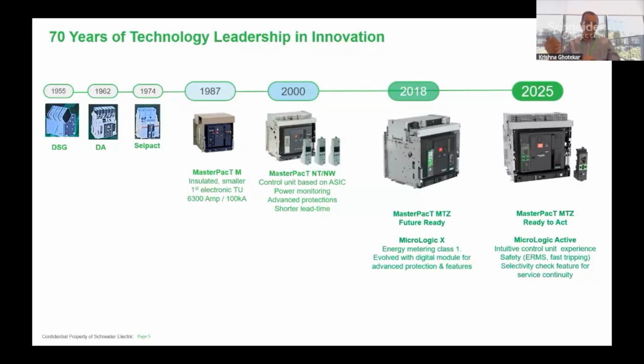Now this Active is basically an upgrade or addition to our existing MasterPact MTZ-X type of breaker. So MasterPact MTZ-X is for the high-end features for high-end applications like mission critical applications, whereas MasterPact MTZ, which is ready to act, is covering all the standard applications. So what do I mean by standard applications? Wherever you don't need power quality embedded in the breaker. Of course, you can add on a power meter with the THD, with the harmonics, and so on. But embedded inside the circuit breaker, if you don't need harmonics, if you don't need advanced protections, what are those advanced protections? Like reverse power, under voltage, over voltage, and so on.